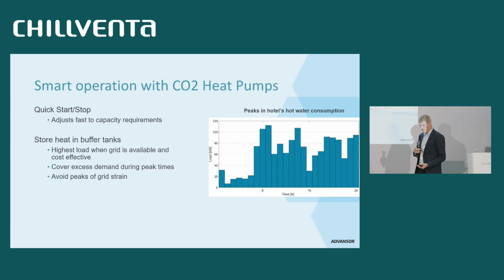COP, of course, is important, but I think it's even more important to look at how we operate the heat pump. So smart operation is really important to get the overall best economy in the system. One of the benefits with the CO2 heat pumps is that we can start and stop really fast. We can adjust the capacity to the heating demand. And if we look at the table I have here on the right side, it shows the hot water consumption from a hotel. And now all of us most likely stay at a hotel this week, and we know that from 7 o'clock in the morning till 9 o'clock, it's really hot water consumption in a hotel. That's where everybody takes the shower in the morning. And from midnight till 7 o'clock in the morning, the hot water consumption is really low.